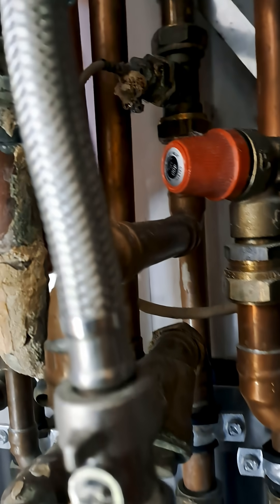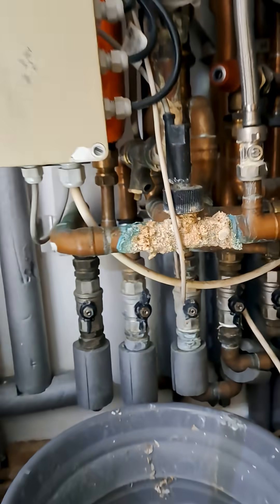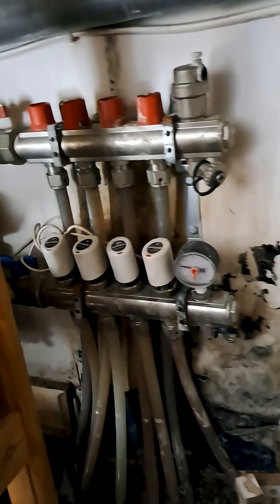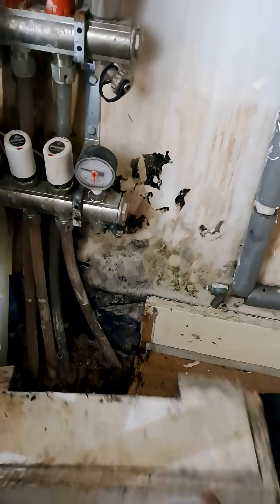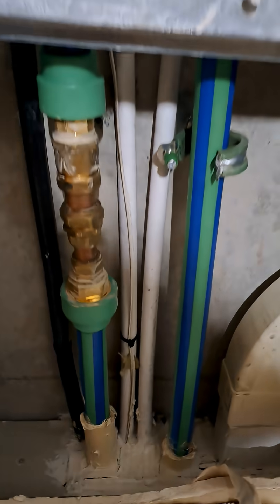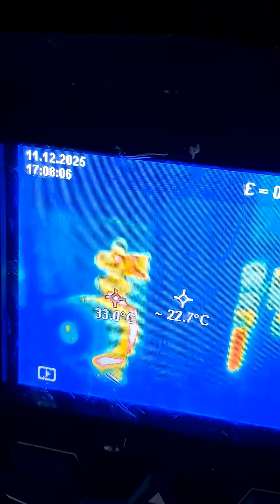There's a leak on the HIU — I want the HIU replaced. I also had to bypass an actuator on the heating circuit and on the floor heating, and bypass something else as well. The pipework is done with what I could find on me, and I had to get an extra zone open. As you can see, there were only a few zones opening up.